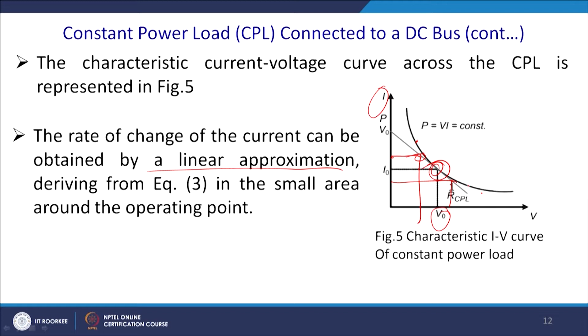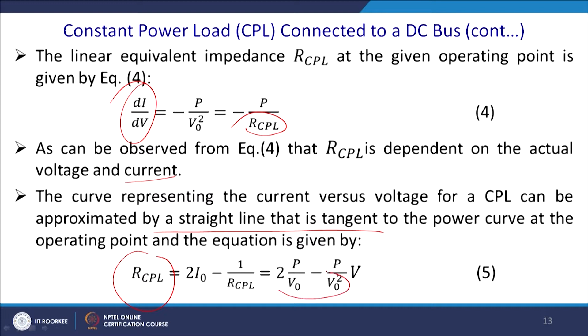At this point you have one tangent and at another point a different tangent, and essentially this gives you the di by dV characteristic. This curve represents the current versus voltage for the CPL and can be approximated by a straight line tangent to the power curve at the operating point, and the equation can be given as: the constant power load current equals 2 I0 minus 1 by R CPL times V, that is 2P by V0 minus P by V0 square into V. This will be the overall expression of the resistance. Since this power is constant, ultimately this resistance definitely depends on the output voltage of this DC bus.